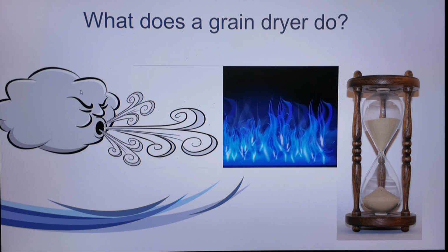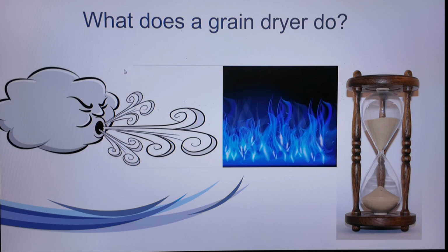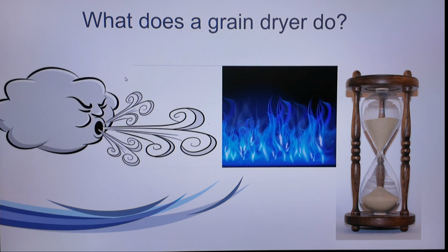On the airflow, I want to hit on one thing. I have seen belt drive fans, when you get into 50 horse and up fans, where the belts get hard and slip without squealing or without smoking, where the belts get real hard and they'll slip and you won't have the airflow you need. So if your belts are more than 5 years old on your fan and you're having drying issues, you put new belts on. Just put new belts on. That way you know that's not the issue.